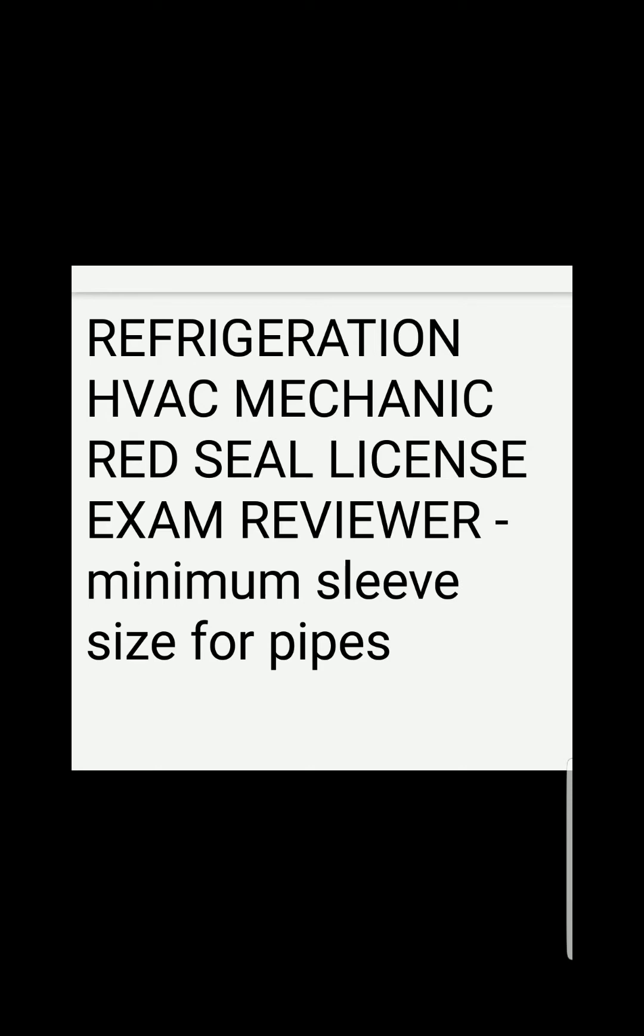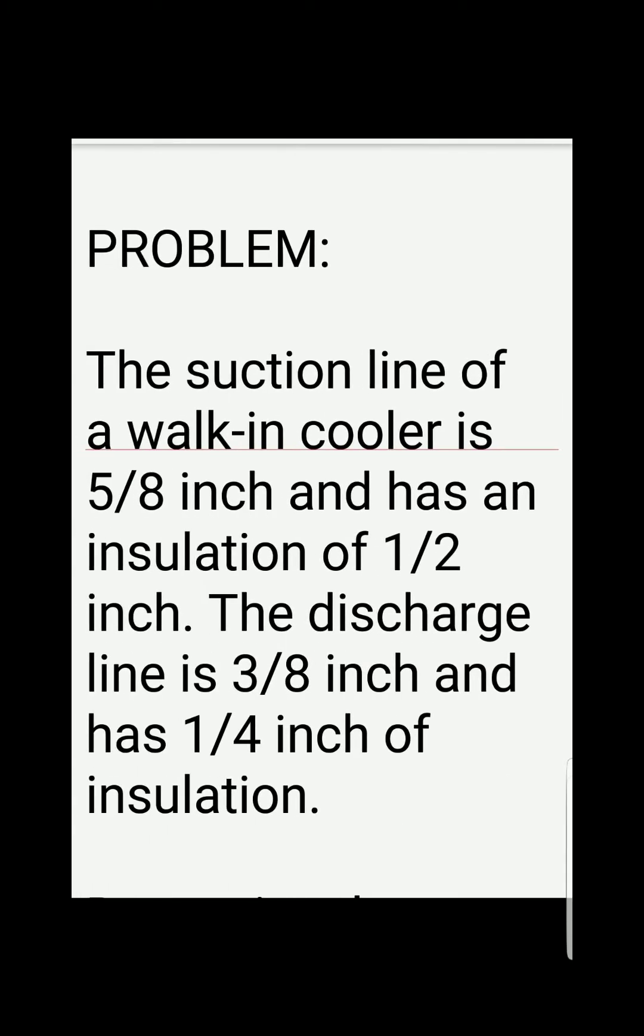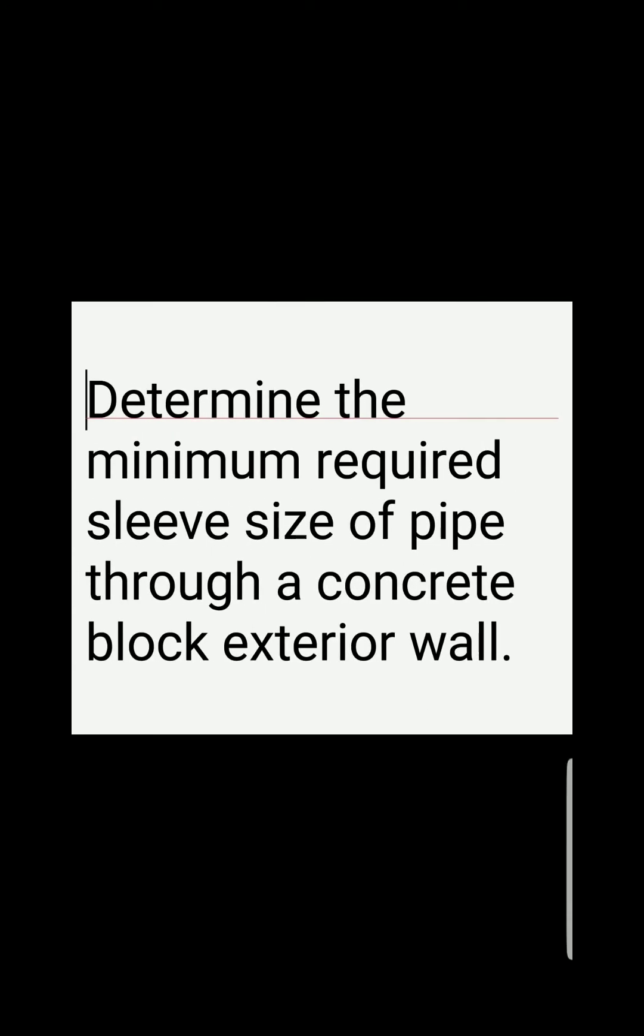We'll start with a problem. The suction line of a walk-in cooler is 5/8 inch and has an insulation of 1/2 inch. The discharge line is 3/8 inch and has an insulation of 1/4 inch. The problem is to determine the minimum required sleeve size of pipe through a concrete block exterior wall.